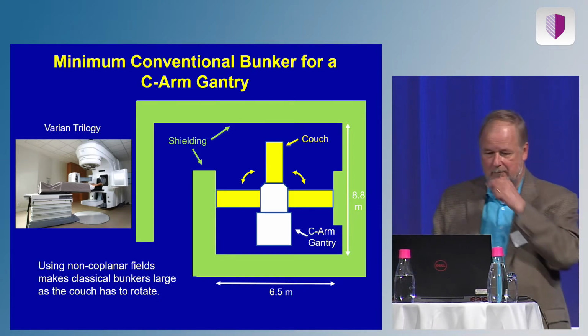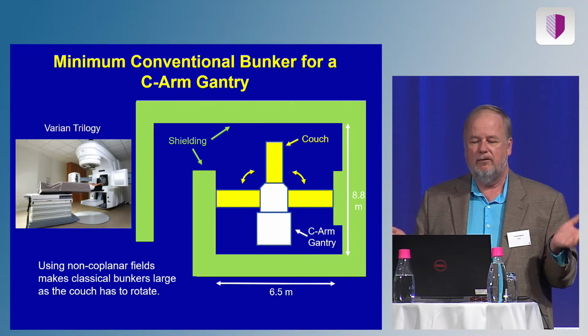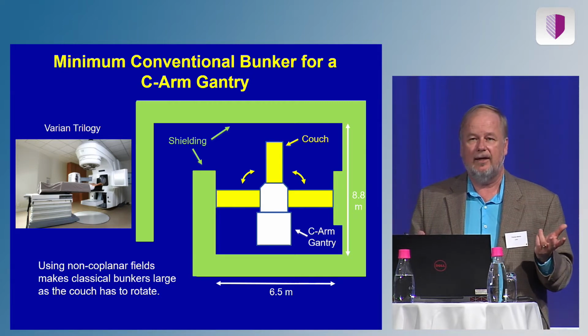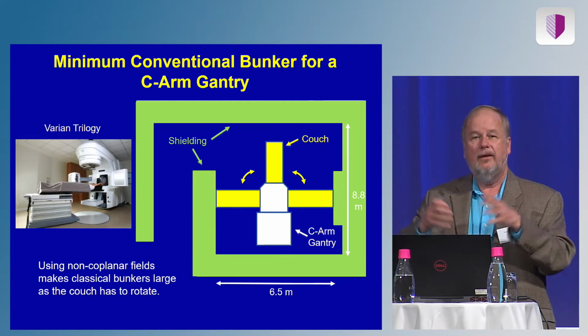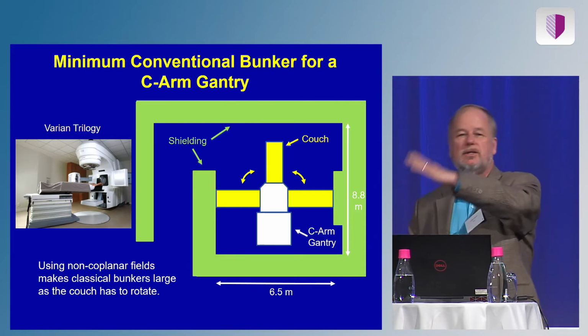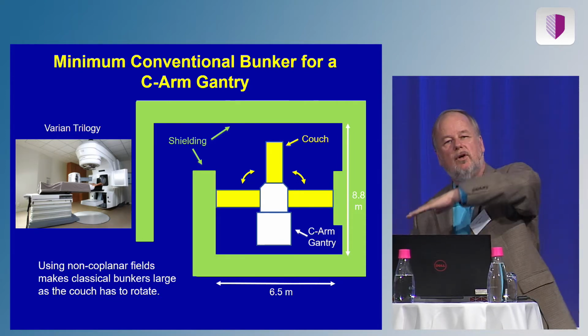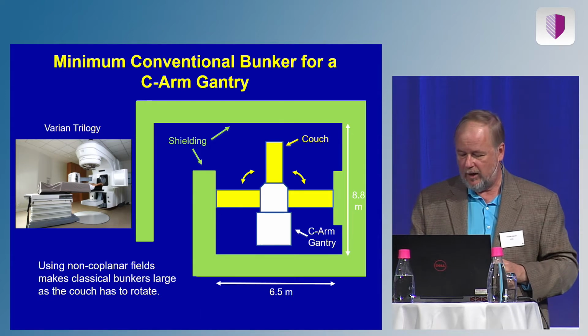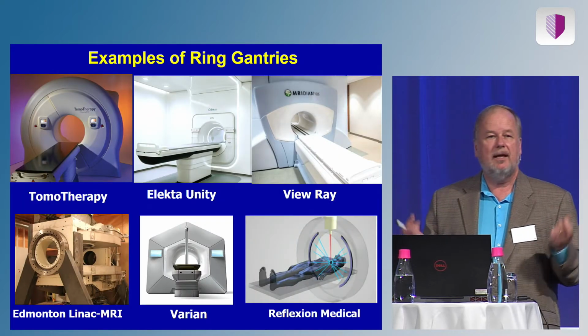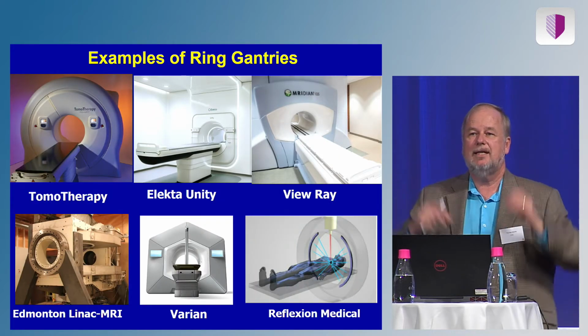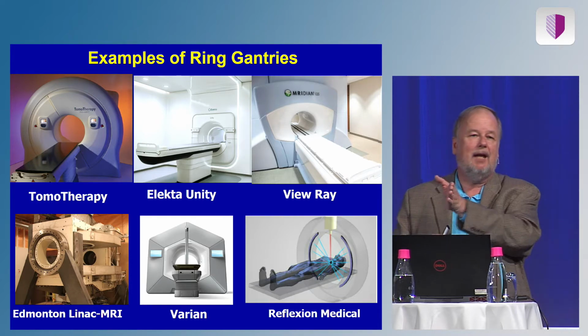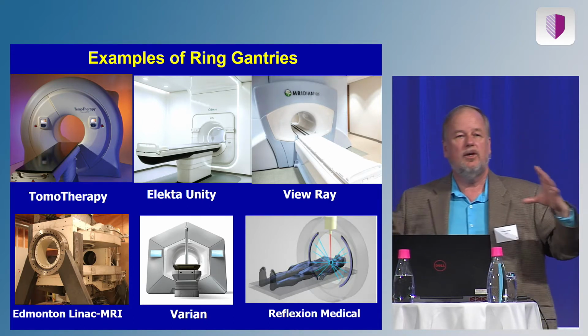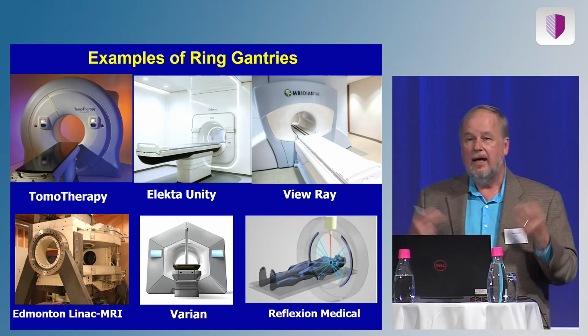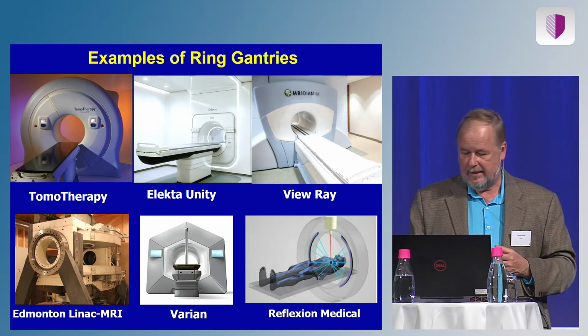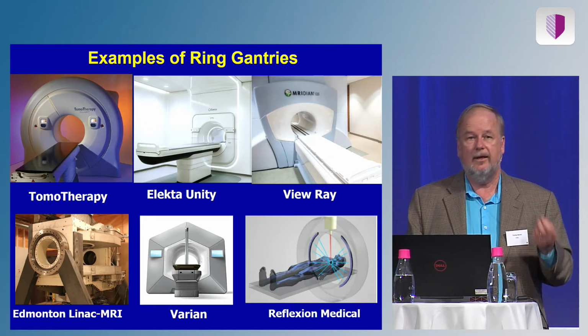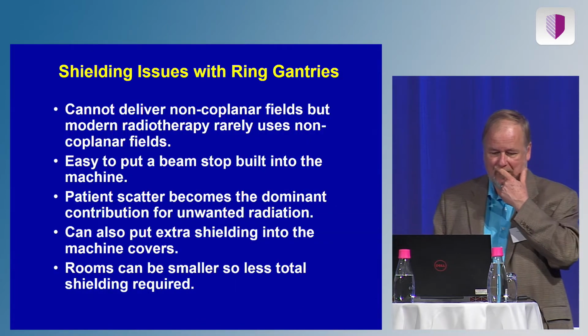If we look at a conventional bunker for a C-arm gantry, the more classical one, the rooms are pretty big because the couches can kick over a long direction. And so you need large vaults. But you see that machines are being developed that are more like CT scanners, and so the couches can't move laterally. And so you can put them in much smaller vaults. And if they go into much smaller vaults, then the construction costs are far reduced.